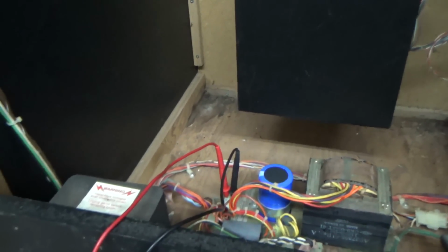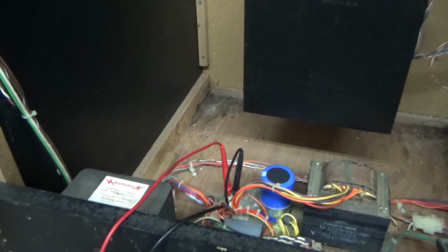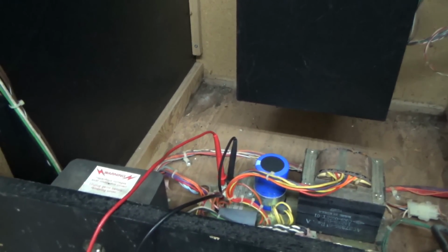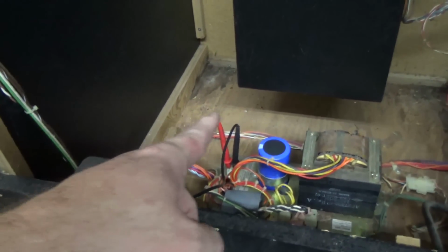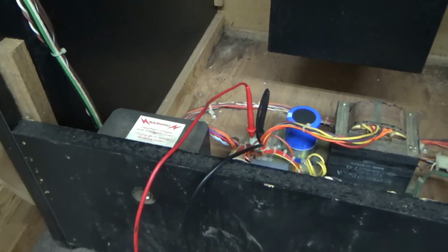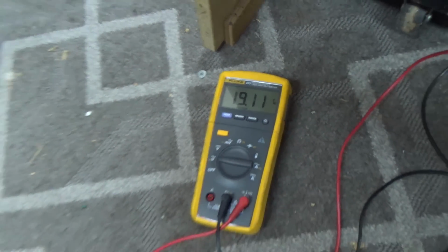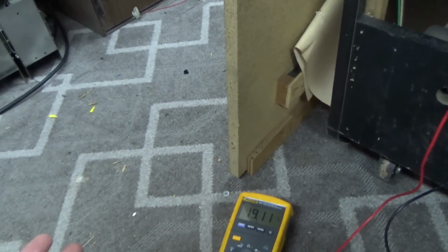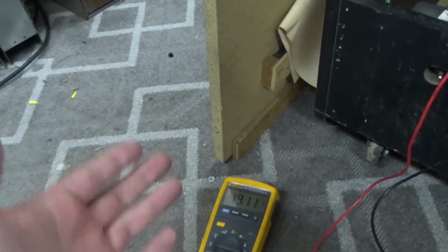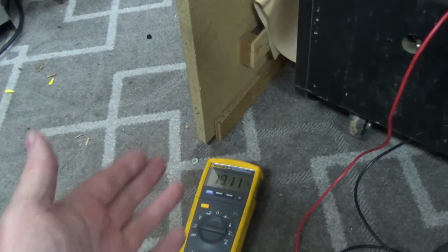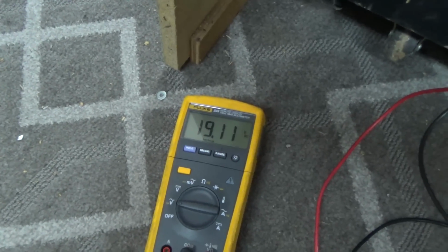That is the 36 volts AC center tap, and the center tap is connected to ground—that's why it's drawn like that on the schematics. So on the 36 volts AC center tap, one leg is giving us 19 volts. Is that a problem? No, because it's a center tap, so it should be half of 36, which is 18—19 is very close.